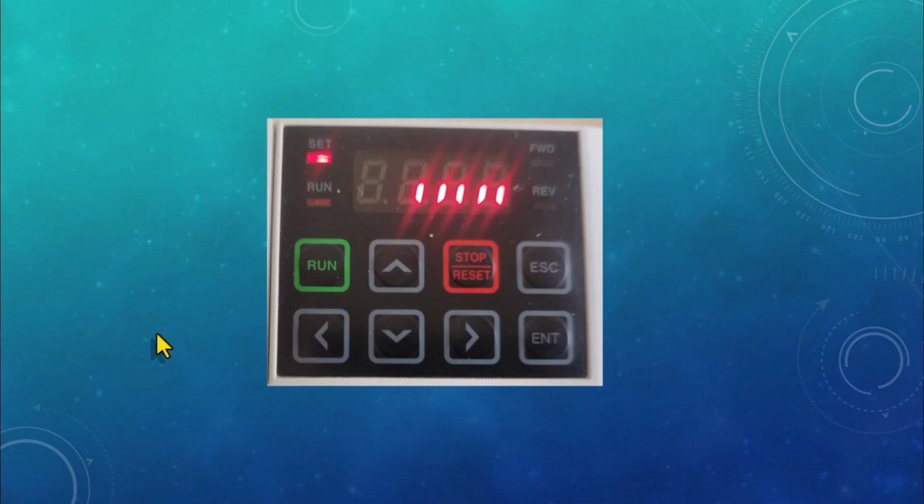In order to change a digital input setting from a normally open state to a normally closed configuration, you must first access the system parameters. In IN87, if the bit related to that digital input is low, meaning it's deactivated, then the contact of that digital input is in the normally open state. And if its bit is high, meaning it's active, then the contact is normally closed.